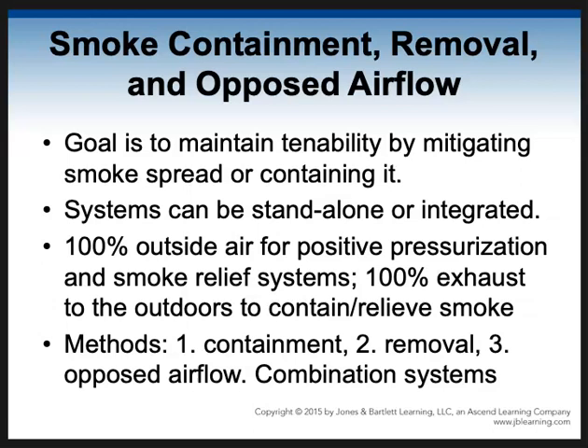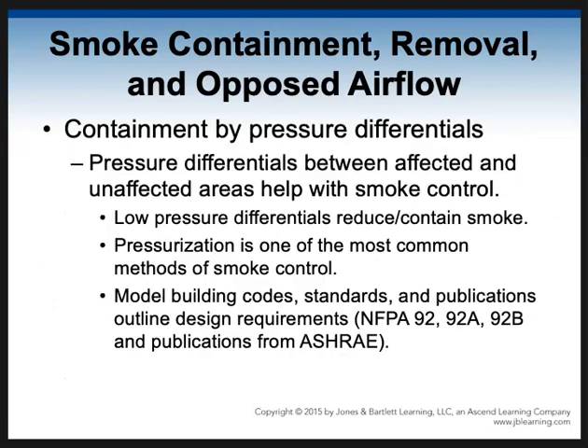So 100% outside air for positive pressurization, 100% exhaust to the outdoors to contain or relieve smoke. So remember I said 3 methods. We're going to contain it. Usually that's done with passive. We're going to remove it, or we're going to oppose it, that smoke. So most of the time, especially in these bigger buildings, it's going to be a combination of all 3 or 2 out of the 3. So let's talk about containment. We can contain it by passive means, but we can also contain it by pressure differentials. So pressure differentials...